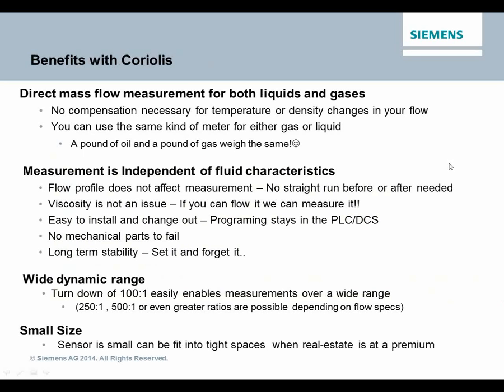All right. So with Coriolis, because of the way it works, there is no compensation necessary, as I mentioned, for temperature or density changes in the flow. It doesn't really matter. You can use the same kind of meter for gas or liquid. You can use the meter that you buy to measure water or helium. Same exact meter. You don't have to change the meter out because a pound, of course, always weighs the same. And again, Coriolis is not affected by process fluid characteristics.